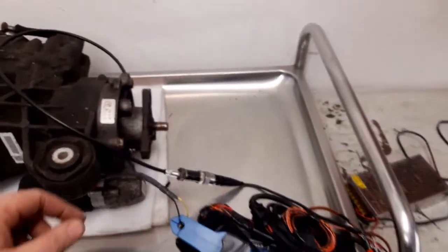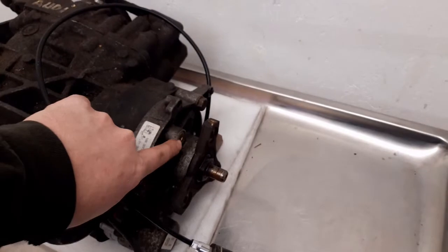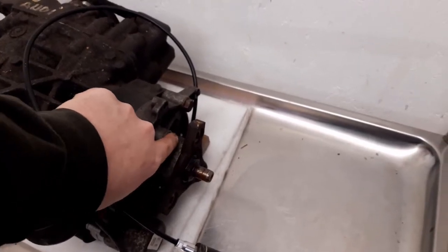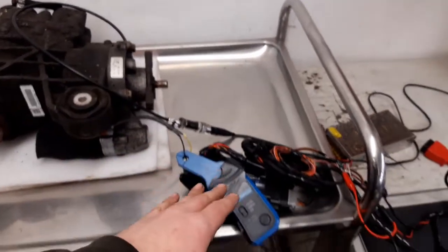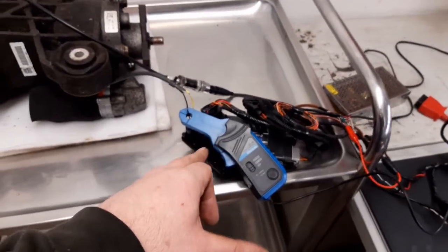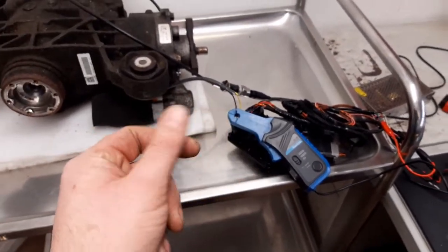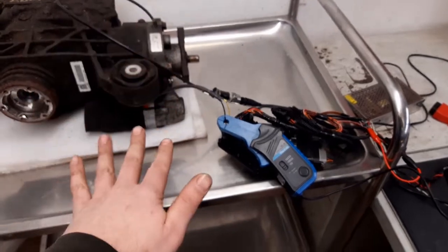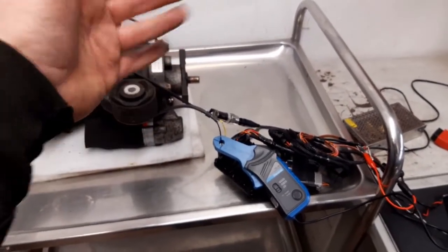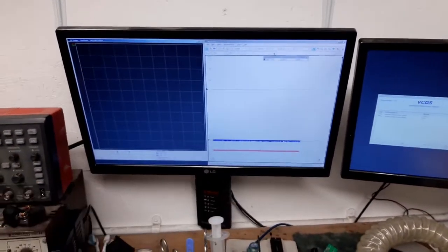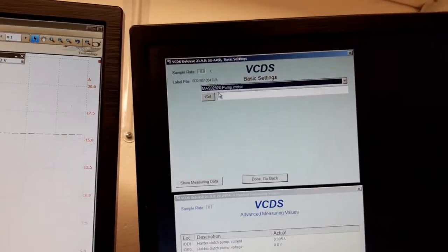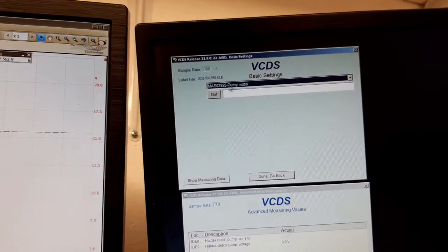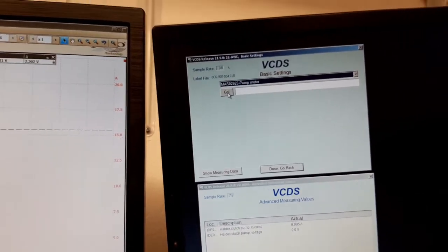The basic idea is we hit the 44 bar pressure release valve. The intelligent motor controller inside the control unit senses the drop in current that it takes, because obviously there's no work being done once the pressure release valve opens. But we'll watch a data log and then you can see what happens. Right, we'll pick the basic settings for the pump motor and we'll start running the pump learn.